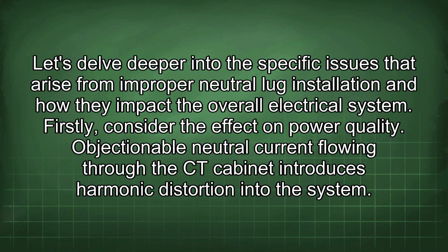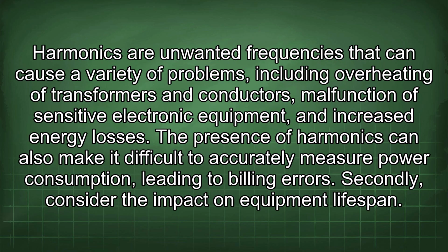Let's delve deeper into the specific issues that arise from improper neutral lug installation and how they impact the overall electrical system. Firstly, consider the effect on power quality. Objectionable neutral current flowing through the CT cabinet introduces harmonic distortion into the system. Harmonics are unwanted frequencies that can cause a variety of problems, including overheating of transformers and conductors, malfunction of sensitive electronic equipment, and increased energy losses. The presence of harmonics can also make it difficult to accurately measure power consumption, leading to billing errors.